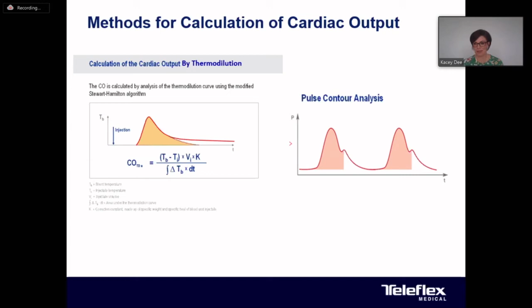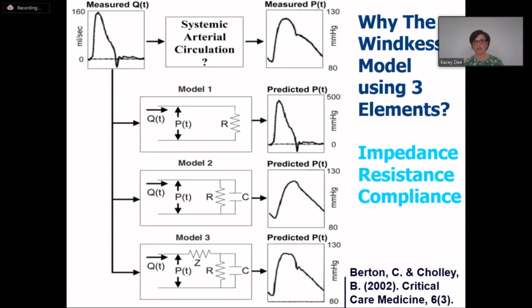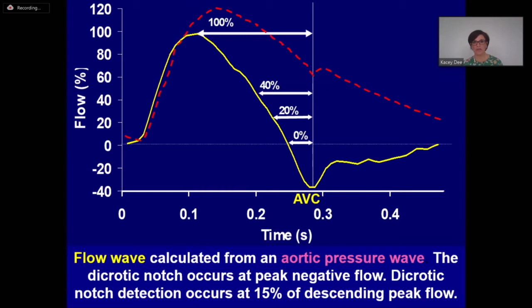So when we look here, the Windkessel model shows how stroke volume ejected from the left ventricle into the aorta becomes a pressure wave. In the wave calculation, we use the 3-element model, compliance, impedance, and resistance, as the measured and predicted AP waves are very similar. In this diagram here, some of you may have seen it in other presentations I've given, this shows the AP measured from the fiber optic sensor on our catheters in red, and the calculated flow wave for the wave algorithm in yellow. The flow is the volume component of pressure, and by calibrating the flow wave, we can measure stroke volume and then cardiac output.